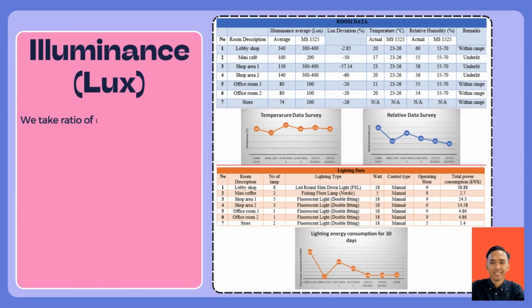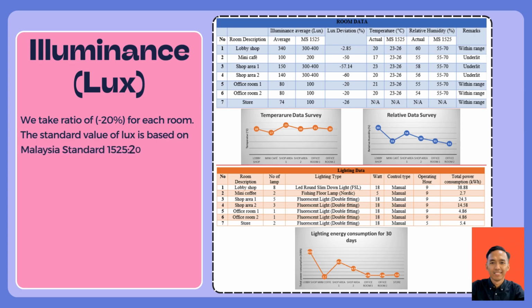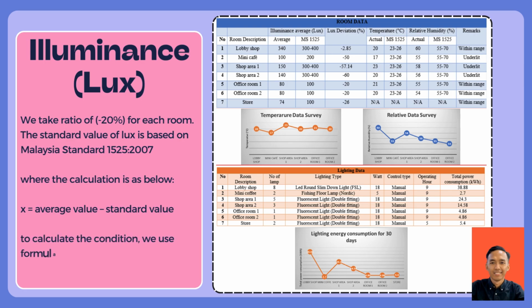So we go to the illuminance lux, where we take the ratio of minus 20% for each room. The standard value of lux is based on Malaysia Standard 1525/2007. The calculation is X equals the average value obtained from the audit minus the standard value from the Malaysia Standard. Then we calculate the condition using the formula Y equals X over the standard value, and convert the answer to a percentage (over 100%).